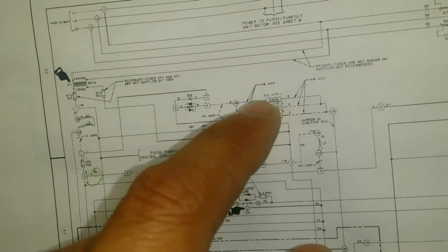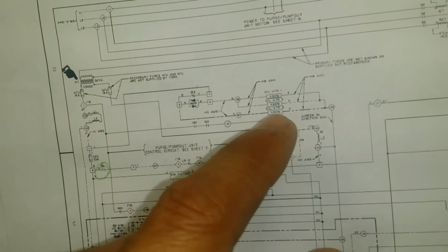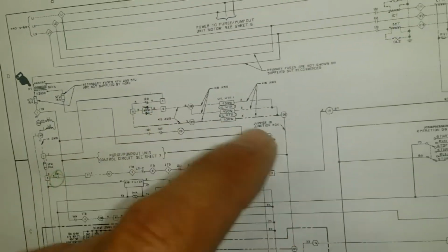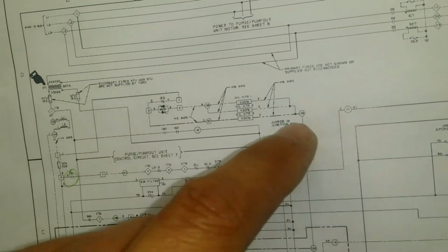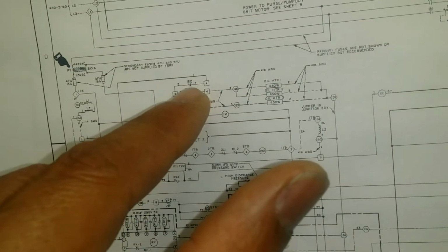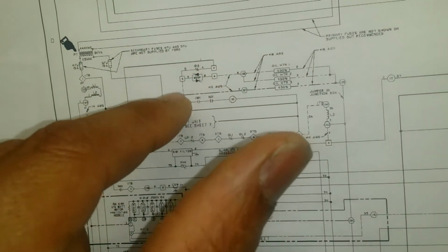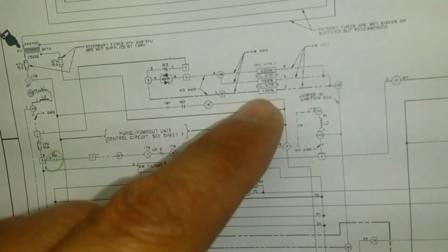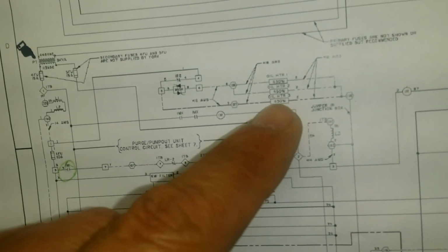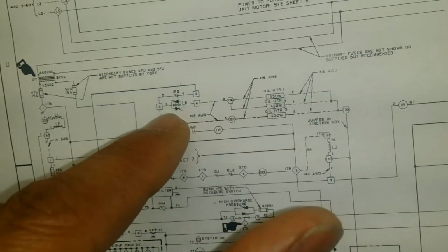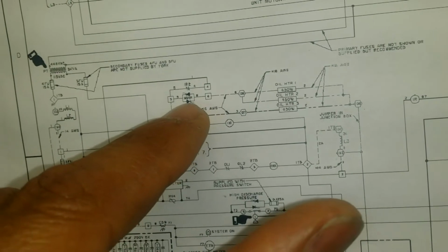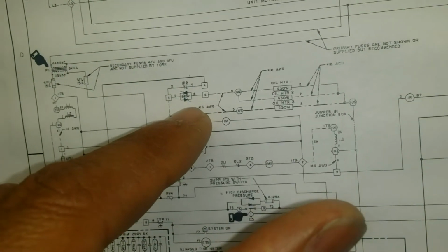Now let's talk about the 3 oil heaters. It's 3 of them, and if you notice, when IR is de-energized, the compressor, we know, is off, but it also causes this contact over here to always keep number 3 heater energized. Number 1 and number 2 heaters only come on whenever this SSR is commanded shorted by the microprocessor.